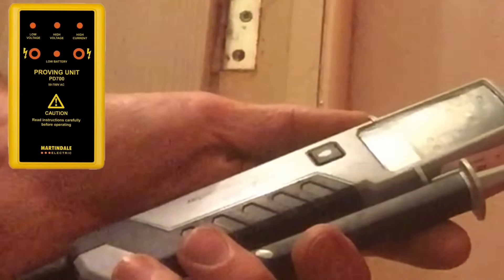I'm going to undo these two screws and locate the rear of the board where the incoming line and neutral and the outgoing line and neutral are located. We need to prove that our test instruments are working. These can either be proved against a known source or we can use a proving unit. Unfortunately today my proving unit hasn't worked for the first time in about four years, so we'll go against a known source instead.